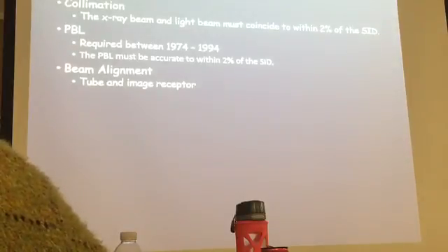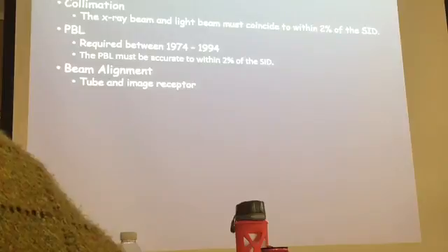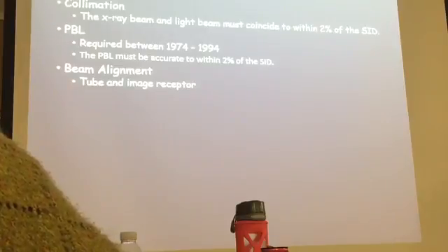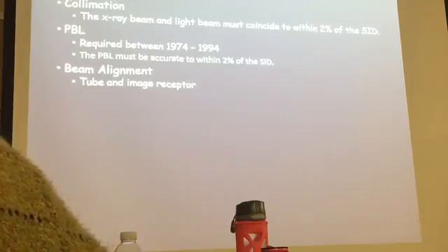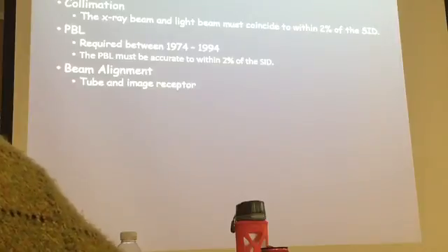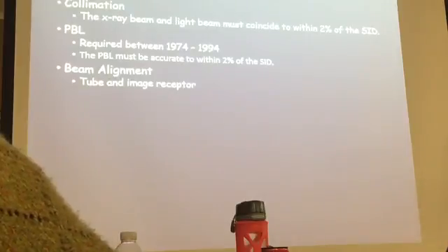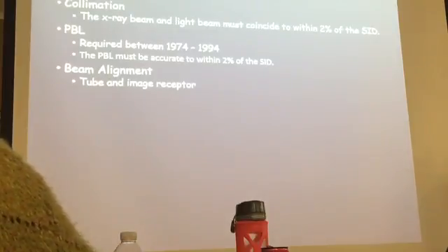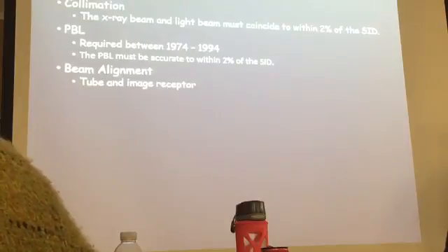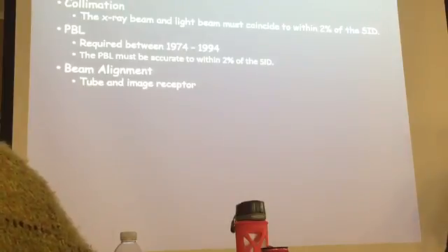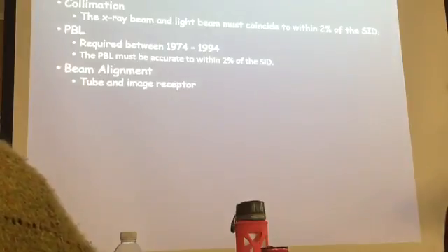There is another testing that is not there, but write it down because it's important. It's called perpendicularity. Here, what you do is you measure, you compare, and see if the X-ray tube is actually perpendicular to the receptor.